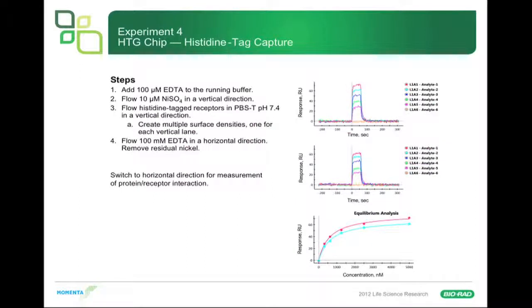The solution was to put a small amount of EDTA — 100 micromolar — into the running buffer to chelate whatever trace metals were present. That was enough, and we didn't get any nonspecific binding anymore. We did studies to confirm robustness: an interaction at time zero compared to one at four hours showed about a 10% loss in activity over four hours, which is acceptable for this type of assay. So 100 micromolar EDTA in the running buffer was the final step, giving us a viable assay with 80% of the receptor active and nonspecific binding not interfering.